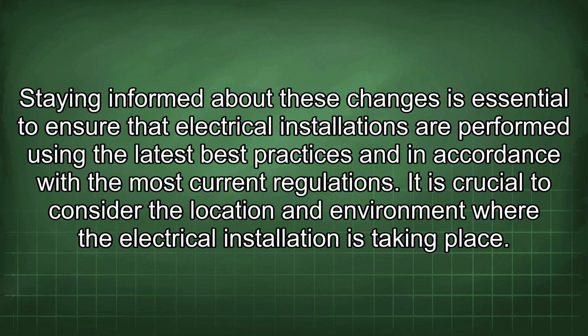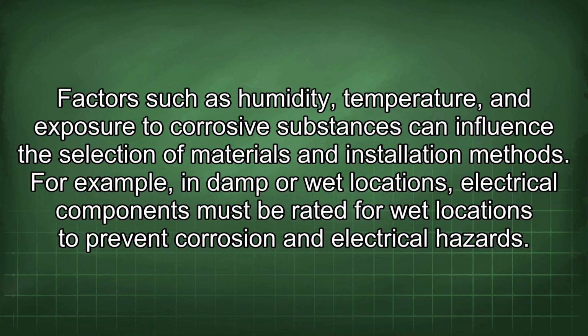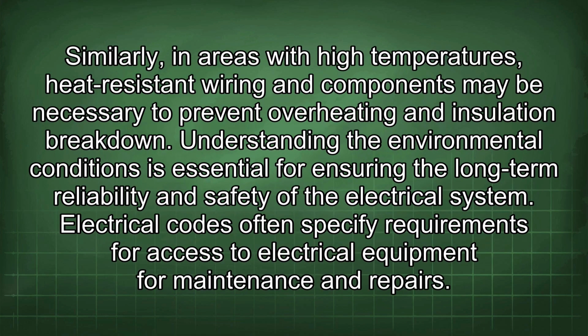It is crucial to consider the location and environment where the electrical installation is taking place. Factors such as humidity, temperature, and exposure to corrosive substances can influence the selection of materials and installation methods. For example, in damp or wet locations, electrical components must be rated for wet locations to prevent corrosion and electrical hazards. Similarly, in areas with high temperatures, heat-resistant wiring and components may be necessary to prevent overheating and insulation breakdown. Understanding the environmental conditions is essential for ensuring the long-term reliability and safety of the electrical system.